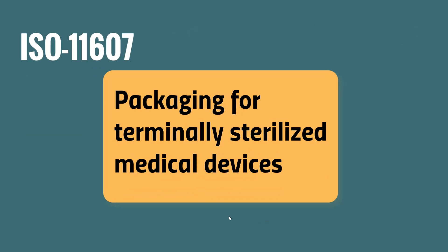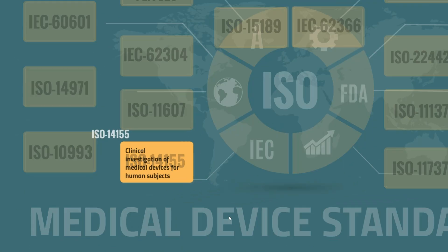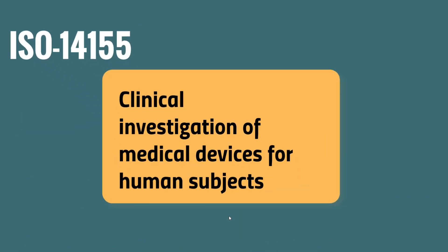8. ISO 14155 — this is the standard for clinical investigation of medical devices for human subjects. This international standard addresses good clinical practices for the design, conduct, recording, and reporting of clinical investigations carried out in human subjects to assess the safety and performance of medical devices for regulatory purposes.